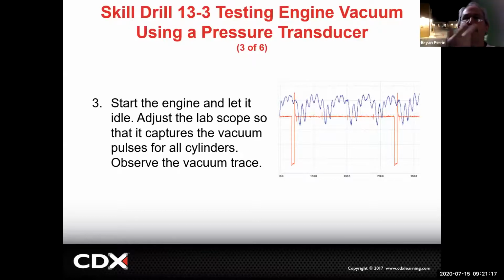So it'd be a vacuum transducer, normally 0 to 30 inches of mercury vacuum transducer. And that would allow me to see those pulses with a great amount of detail.